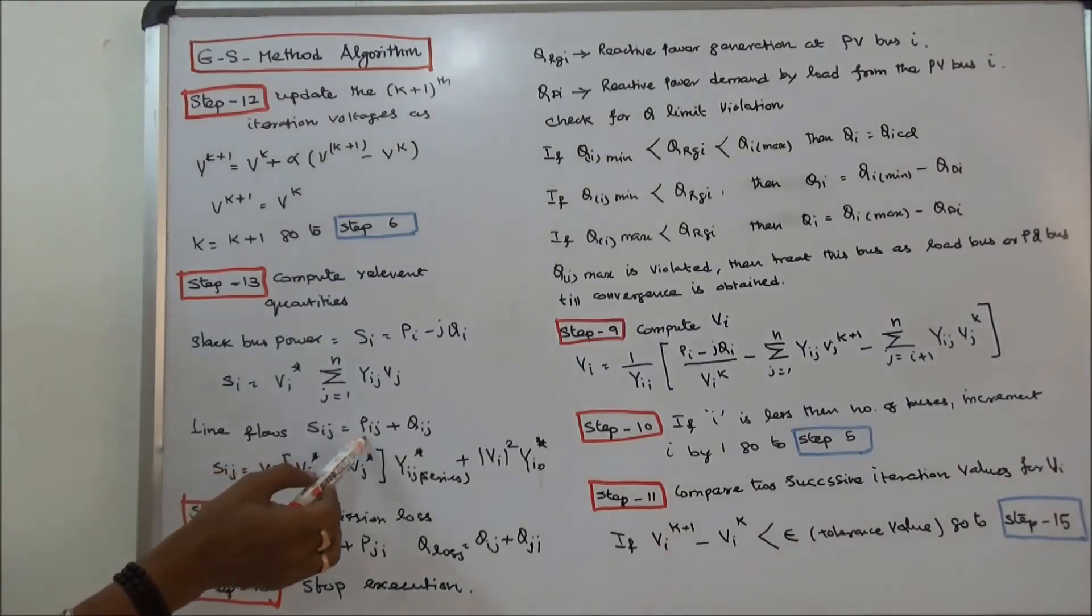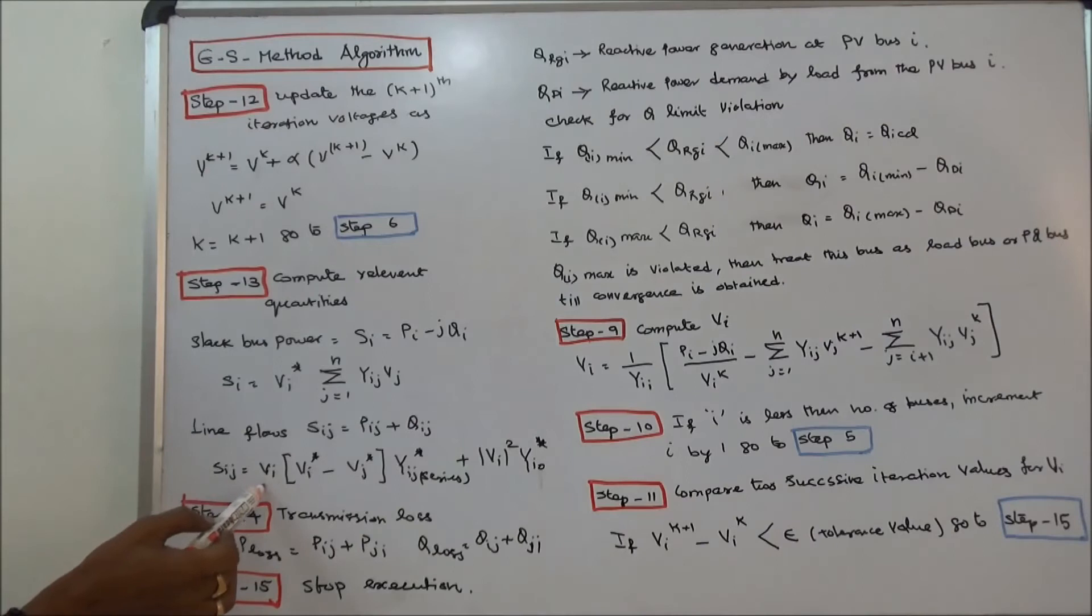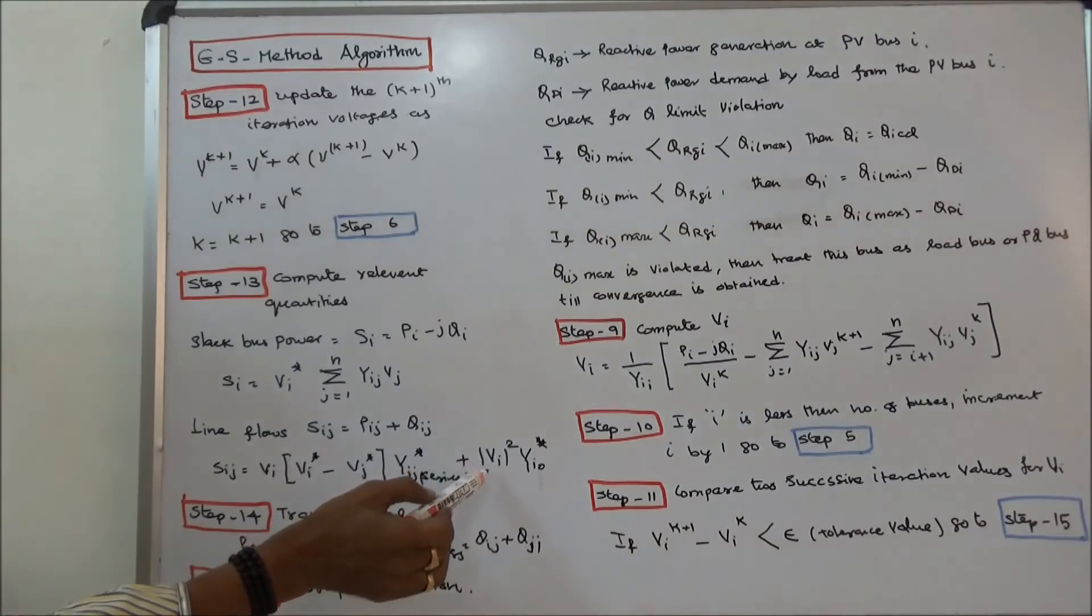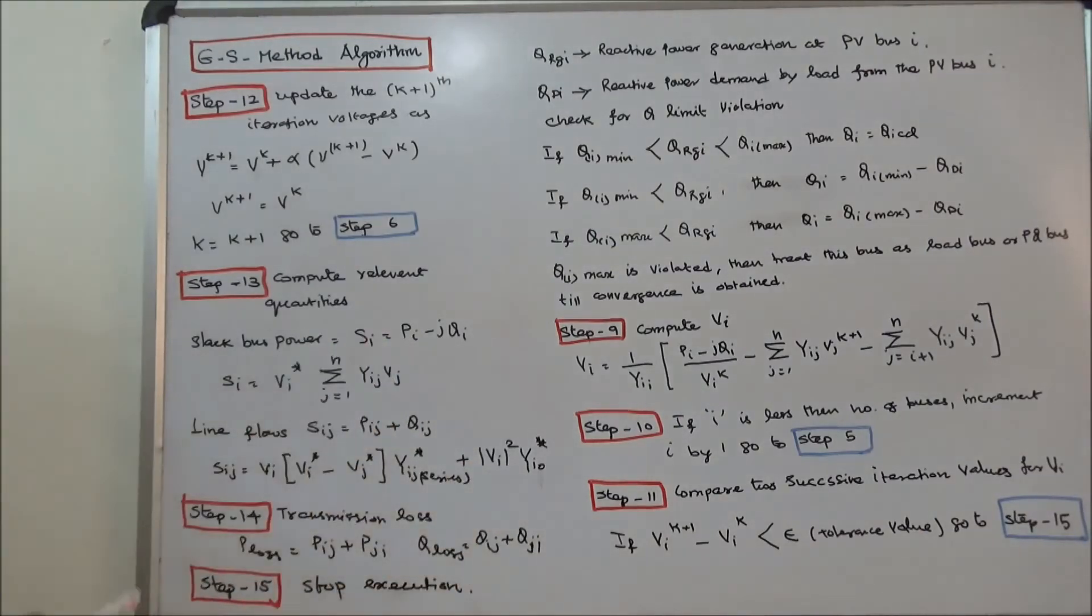SIJ is equal to PIJ plus j QIJ. SIJ is equal to VI into (VI conjugate minus VJ conjugate) into YIJ conjugate series plus VI square into YI0 conjugate. Step 14: Calculate the transmission loss. That is real power loss is equal to PIJ plus PJI. Reactive power loss is equal to QIJ plus QJI.